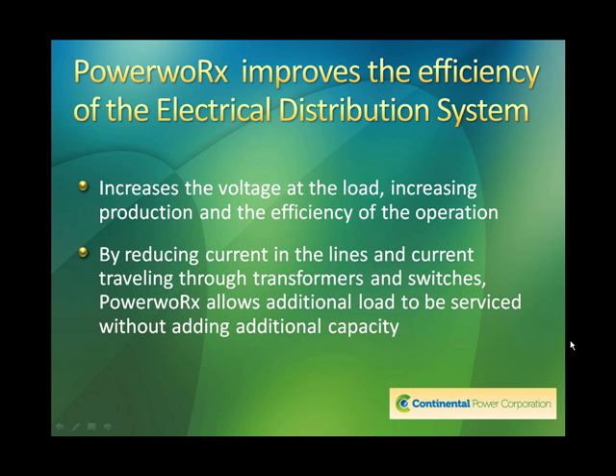Okay, the PowerwoRx improves the efficiency of the electrical distribution system. You know, we've talked about that a little bit. I want to make sure you understand this point. It increases the voltage at the load, and the reason is that we're getting rid of line losses. It increases production and the efficiency of the operation. Voltage losses can wreak havoc on any type of facility. It doesn't even have to be commercial. Residential, the same problem. But when you get into an industrial facility where you have very, very high currents, voltage losses can be significant. It can actually stop the equipment from properly operating. We've seen it many times.